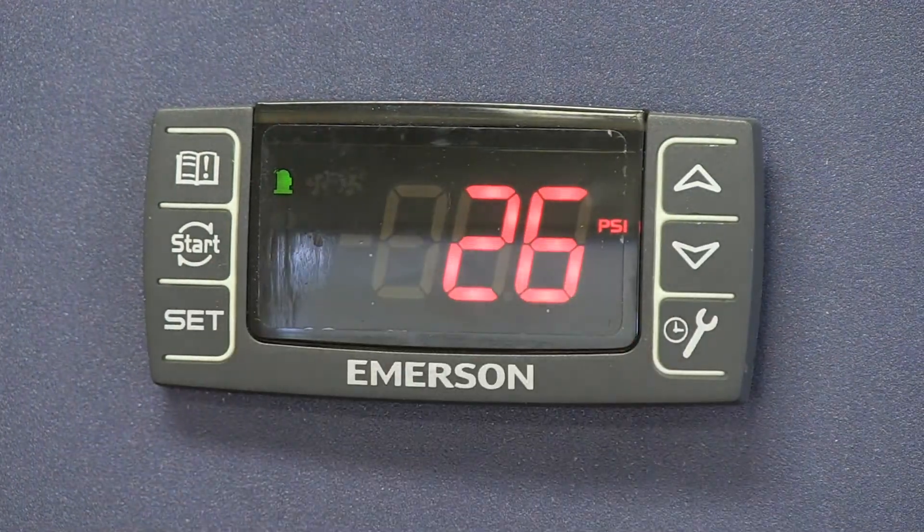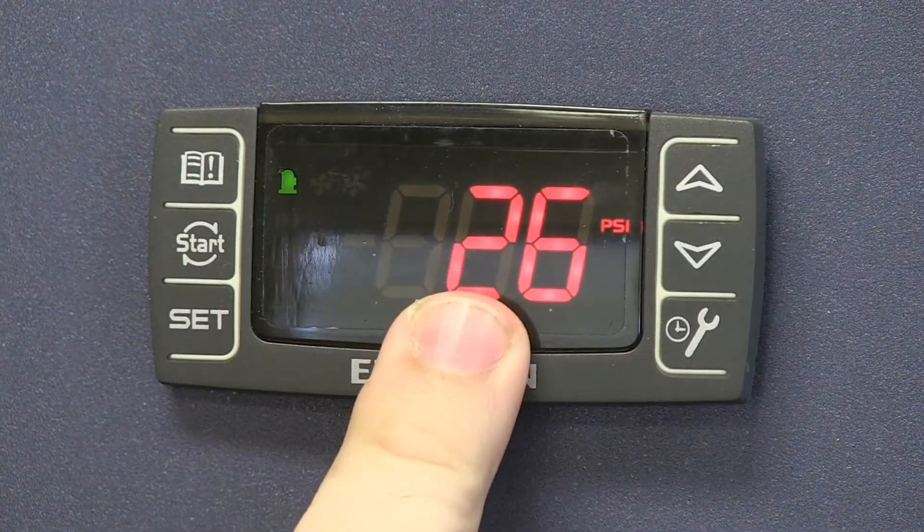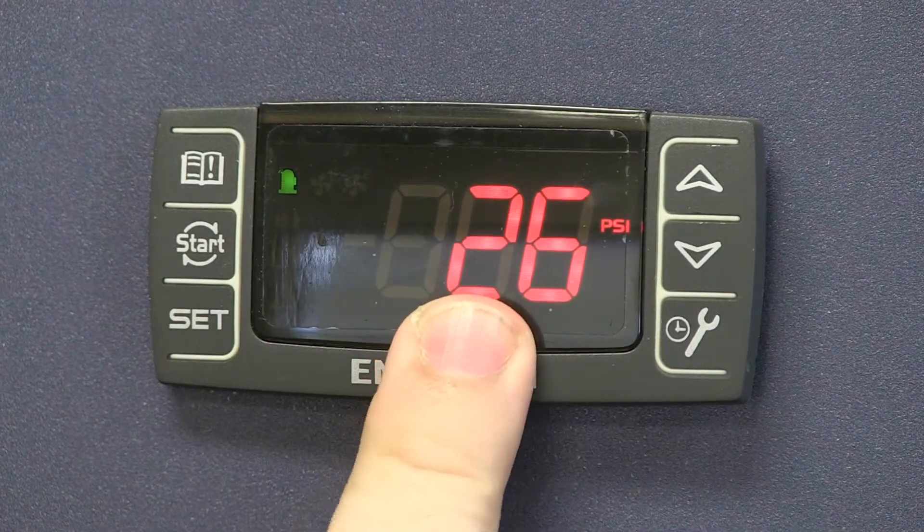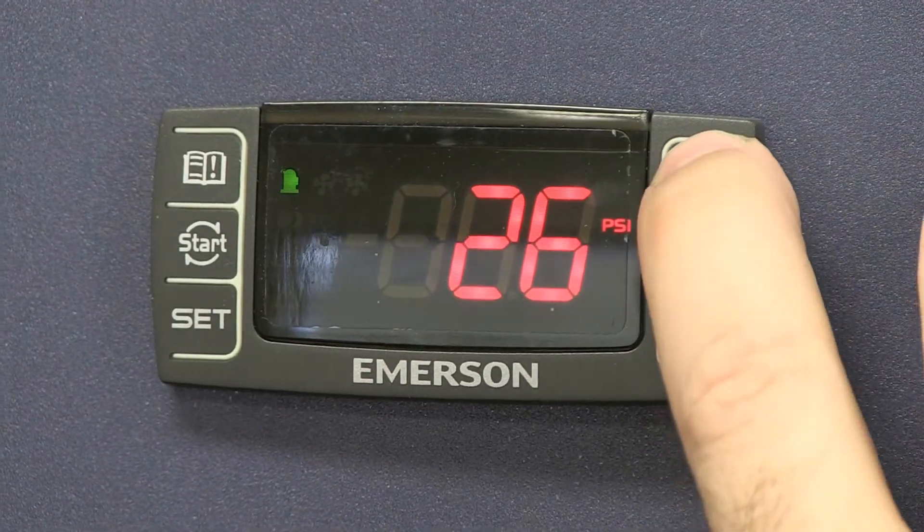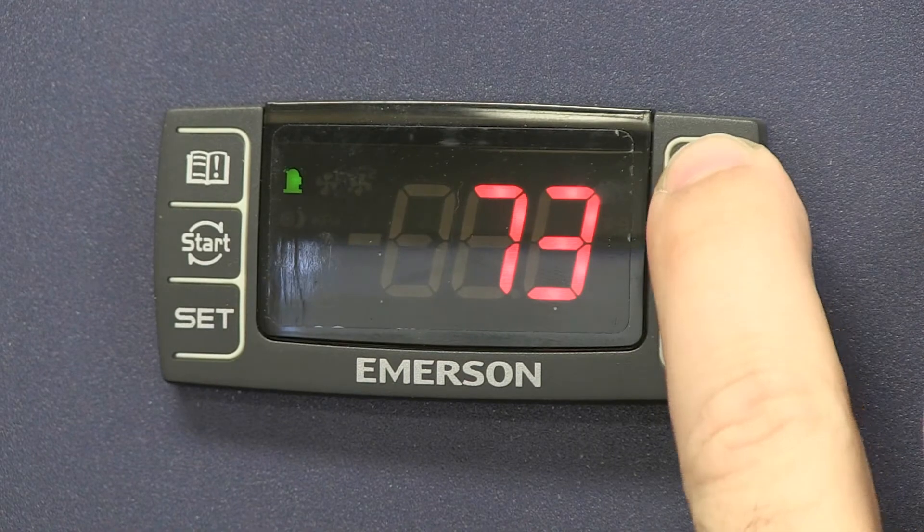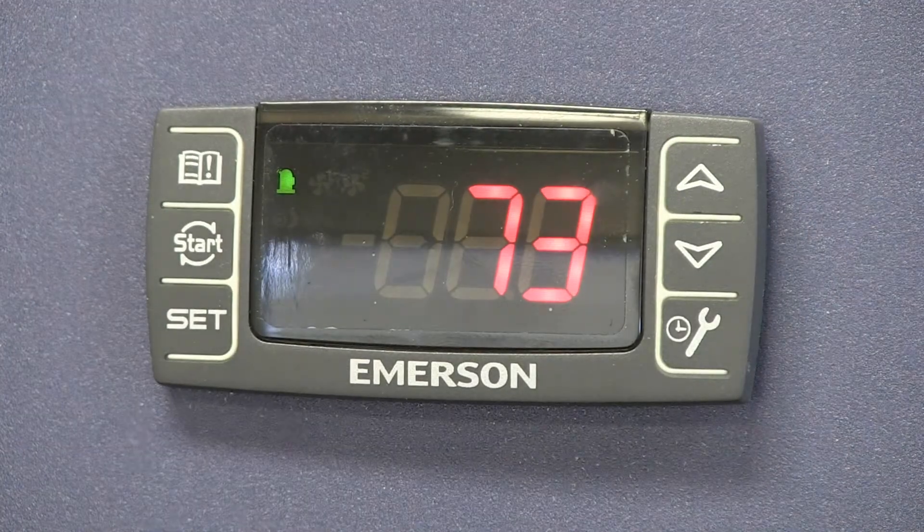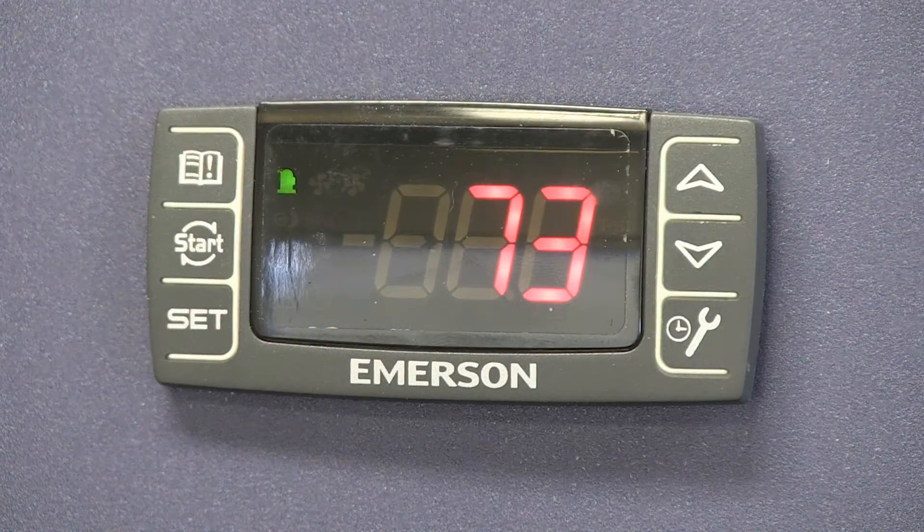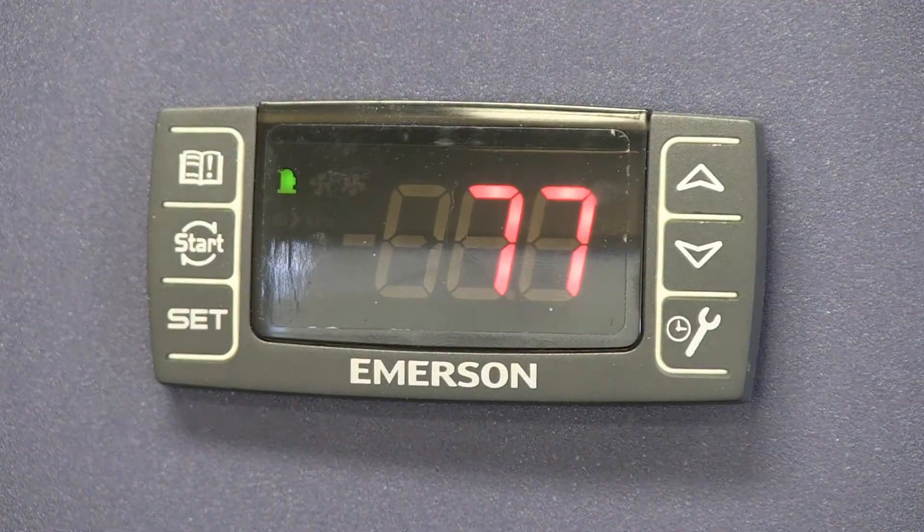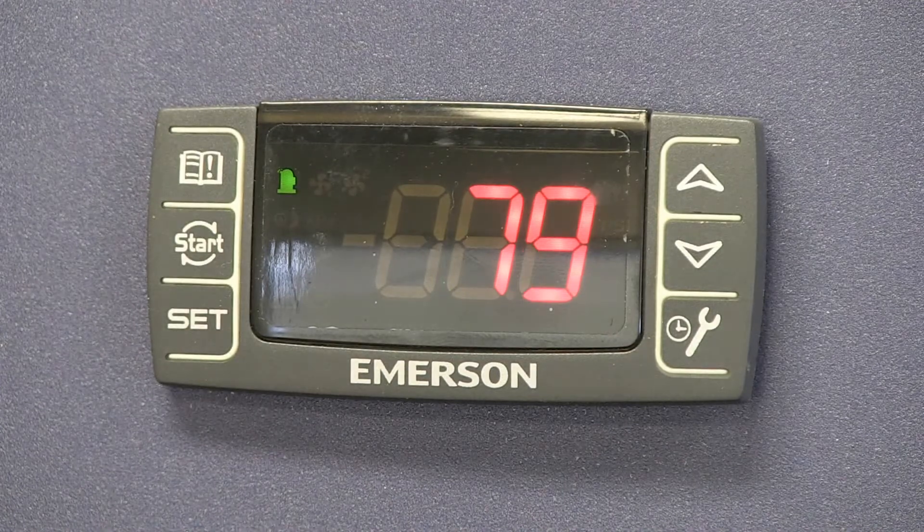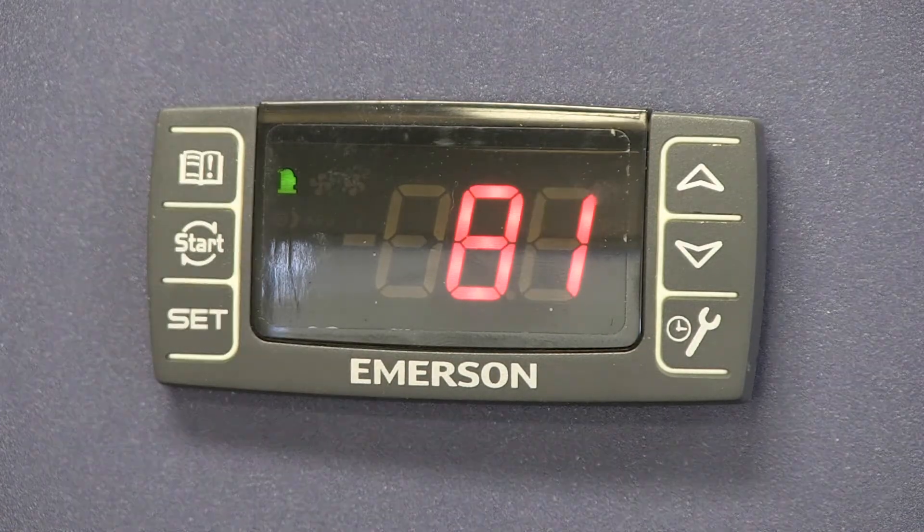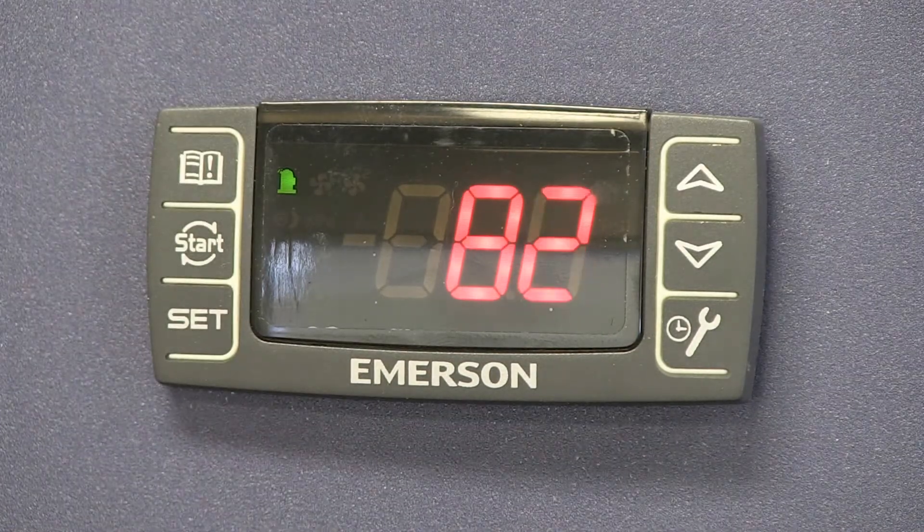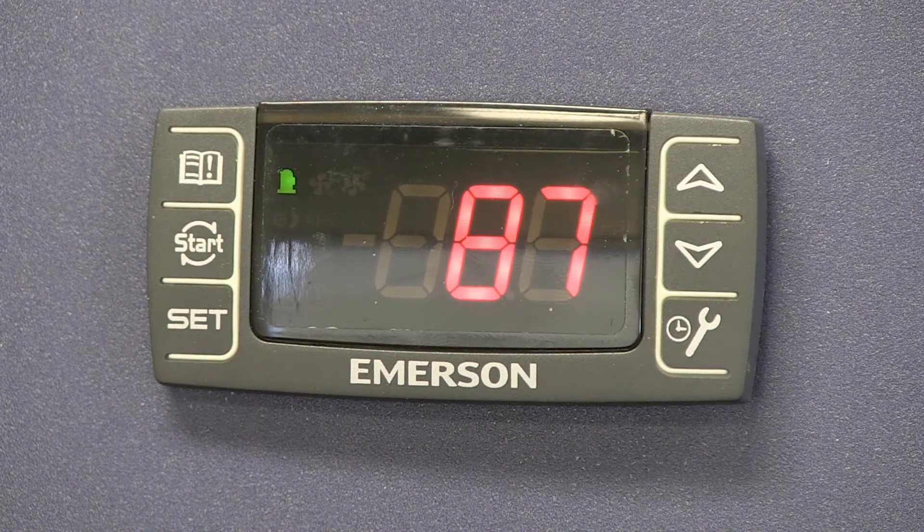Right now we've got a suction pressure at 26 PSI. I'm going to hit this up arrow button that gives us our condensing temperature. So now we're going to raise this up and we should see this now at that new temperature at 90 degrees, that new fan will come on.